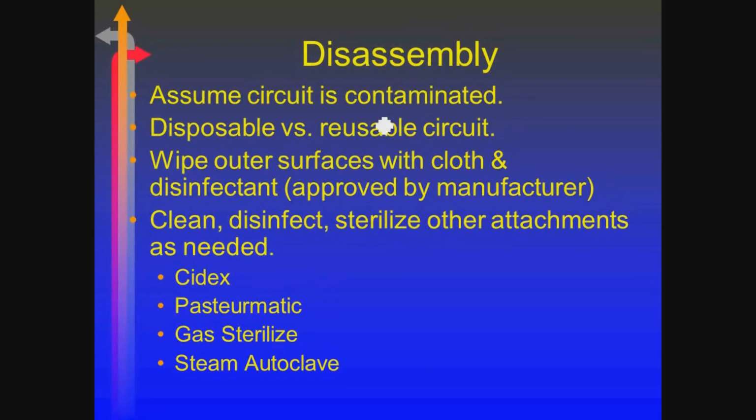We're going to wipe the outer surface with a cleaner and disinfectant. You can't immerse the ventilator inside some sort of pasteurizer. It wouldn't do well. A lot of the touch screens are very sensitive as far as what they can use. Sometimes it's just as simple as using something like Windex to clean the glass. But there are some cleaners that are abrasive, and once the screen gets scratched, it doesn't work really well, as you can imagine. It's like doing that to your iPhone, it doesn't work well.